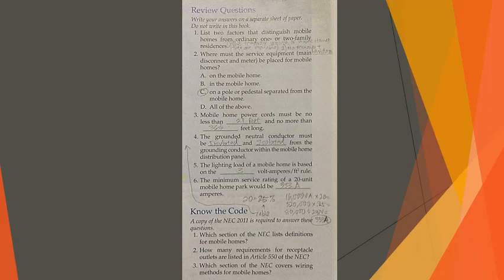Question 3, mobile home power cords must be no less than 21 feet and no more than 36.5 feet long. Question 4, the grounded neutral conductor must be insulated and isolated from the grounding conductor within the mobile home distribution panel. Question 5, the lighting load of a mobile home is based on 3 volt amperes, or 3 VA, per square foot rule. Question 6, the minimum service rating for a 20 unit mobile home park would be 333 amperes.